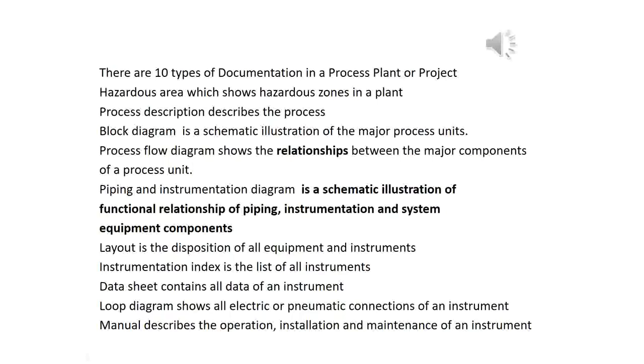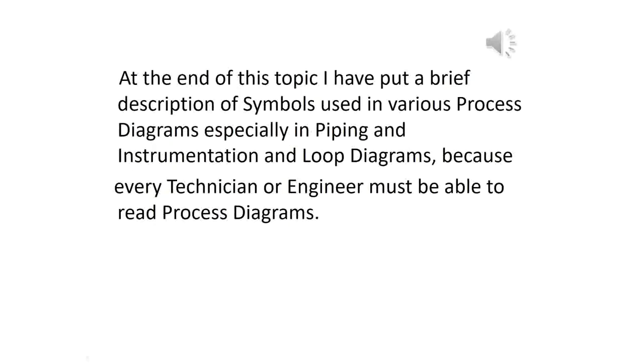6. Layout is the disposition of all equipment and instruments. 7. Instrumentation index is the list of all instruments. 8. Datasheet contains all data of an instrument. 9. Loop diagram shows all electric or pneumatic connections of an instrument. 10. Manual describes the operation, installation, and maintenance of an instrument. At the end of this topic, I have put a brief description of symbols used in various process diagrams, especially in piping and instrumentation, and loop diagrams, because every technician or engineer must be able to read process diagrams.